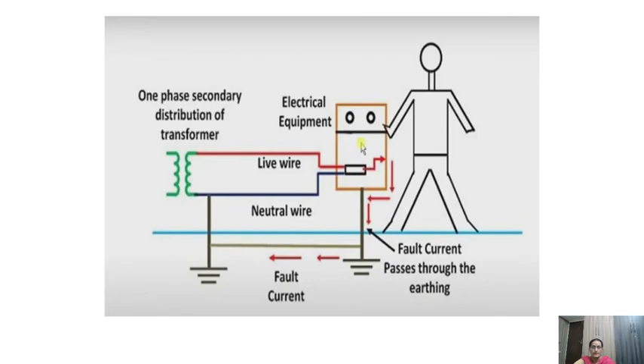So in this case, even if the equipment is not working properly, the operator is not subjected to any electrical shock. He is safe because of the earthing wire. The fault current will flow through the earthing wire. So the need of electrical grounding: it prevents dangerous potential from appearing on the equipment even during electrical faults. It also ensures proper operation of the equipment during fault conditions.